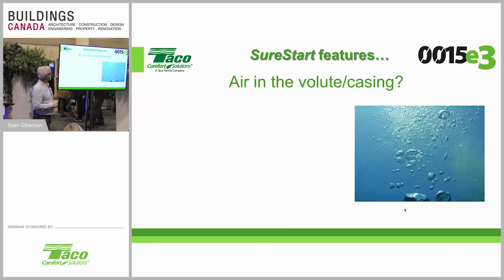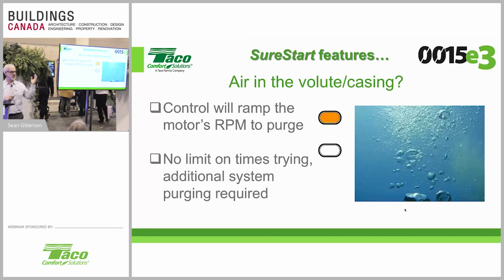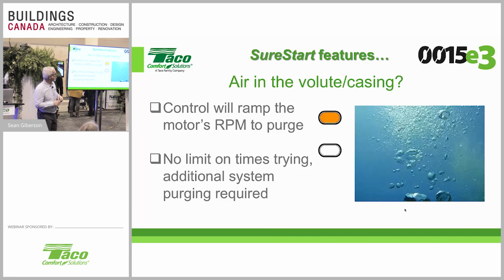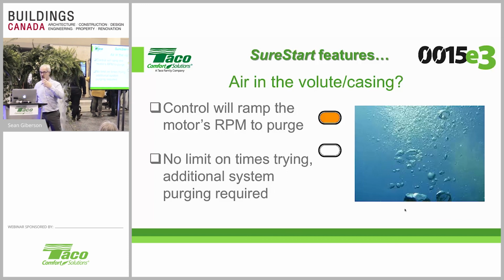In this case there's a whole other piece, and if you ever get an opportunity to do a course, this one I think will impact your systems as much as a circulator will, and that's air elimination. Too little thought is given to what a good air eliminator will do in a system. If we talk about this one, it will speed up and slow down, and it'll try indefinitely, but it'll always go through that mode. So somebody will know before they leave that job site that something's up.